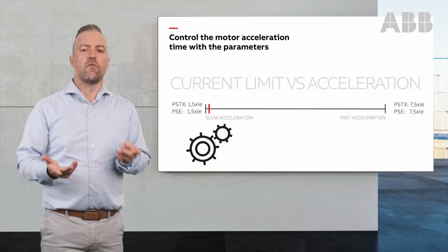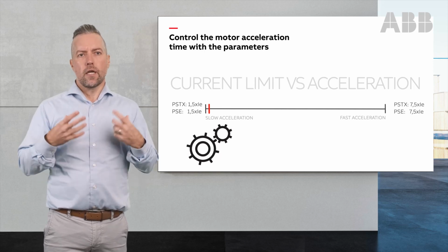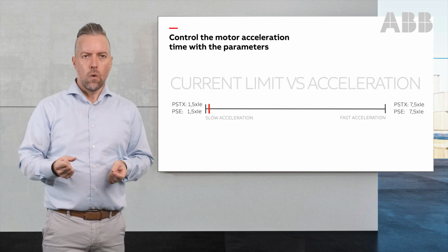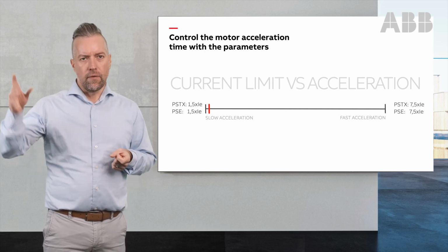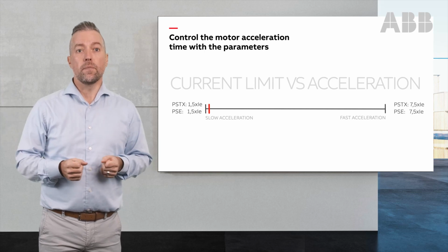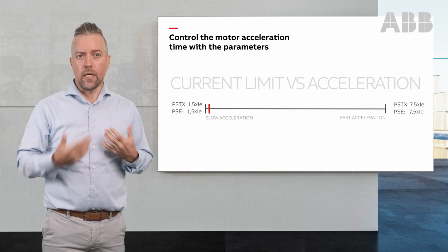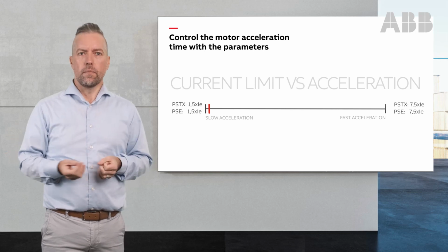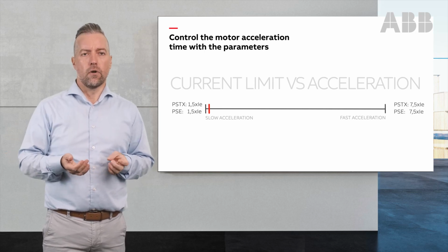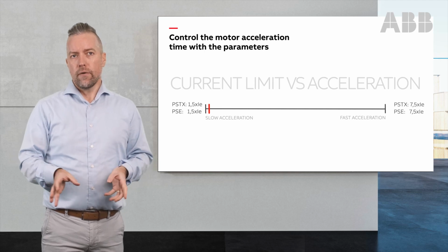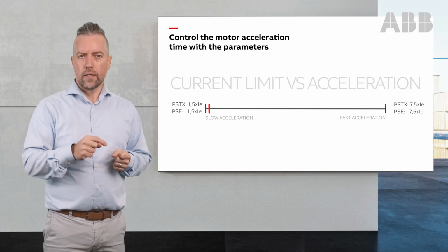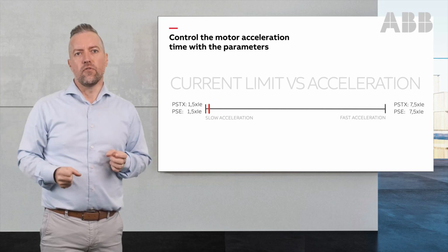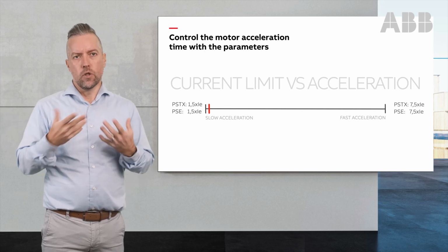But here we need to be really careful, because the motor may not actually start, or it will start but never reach full speed and always be in ramp. And then over time it will trip on electronic overload. So we need to be careful so we know that our application actually gets up to full speed and the motor starts to rotate.